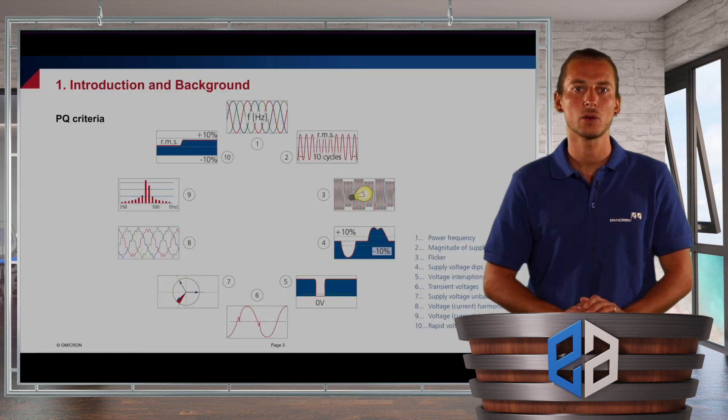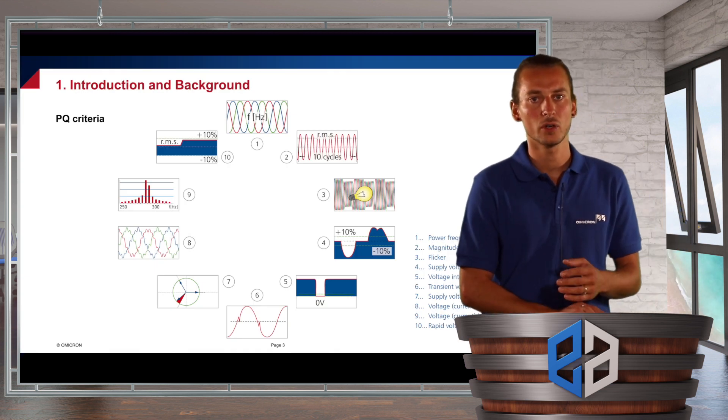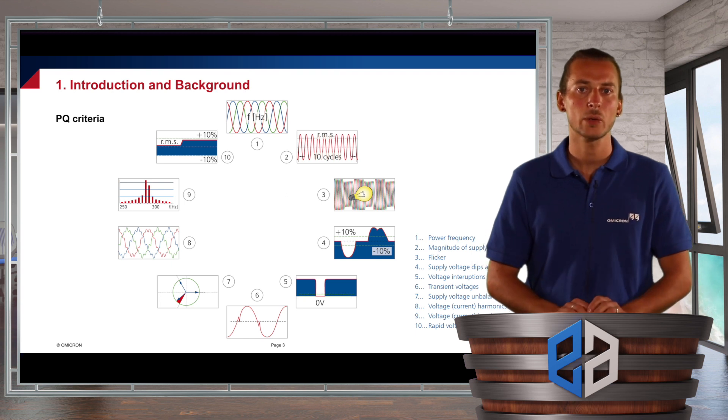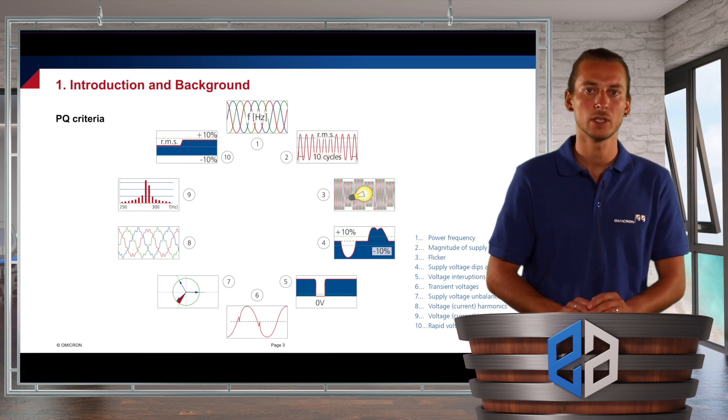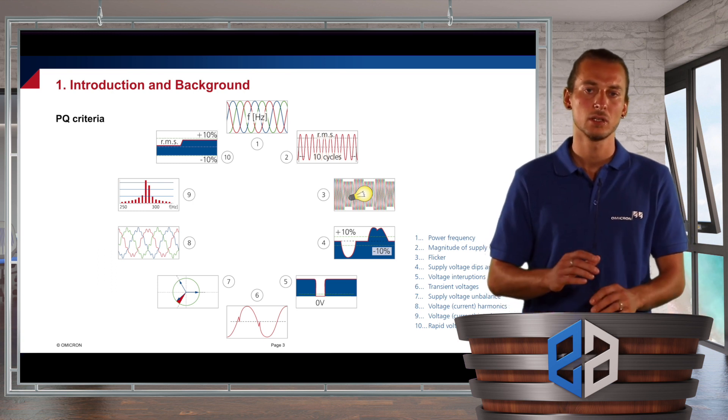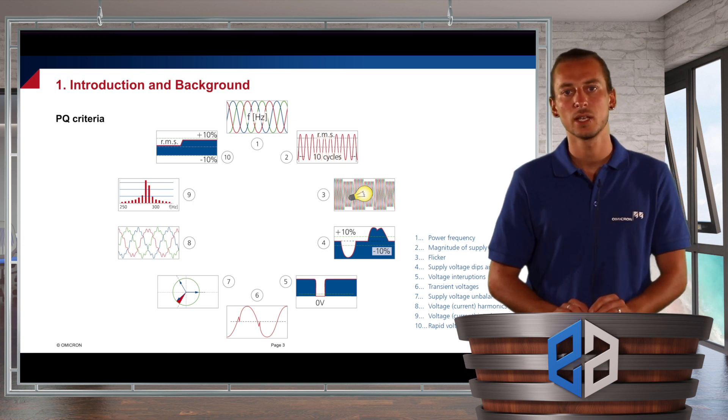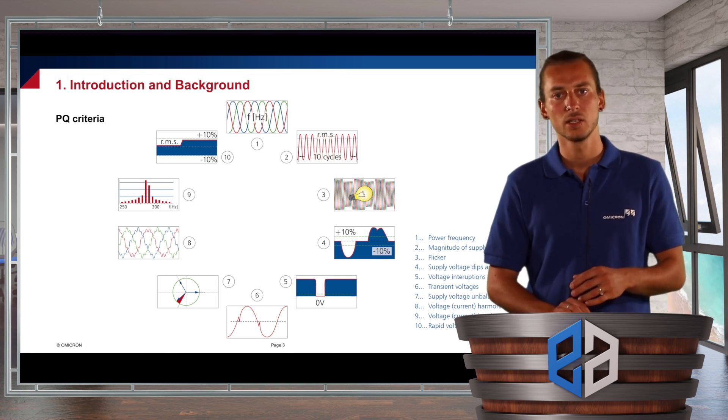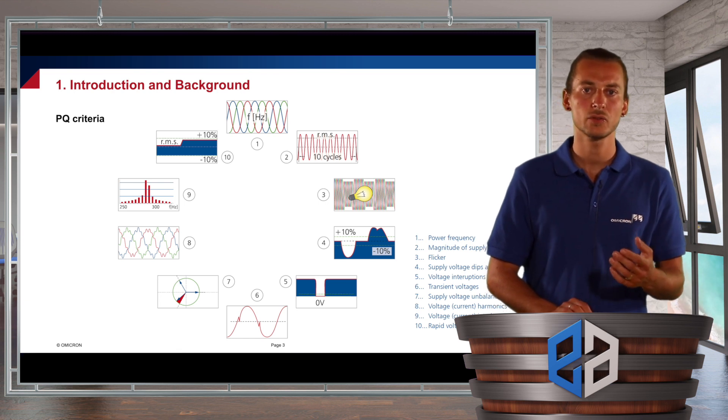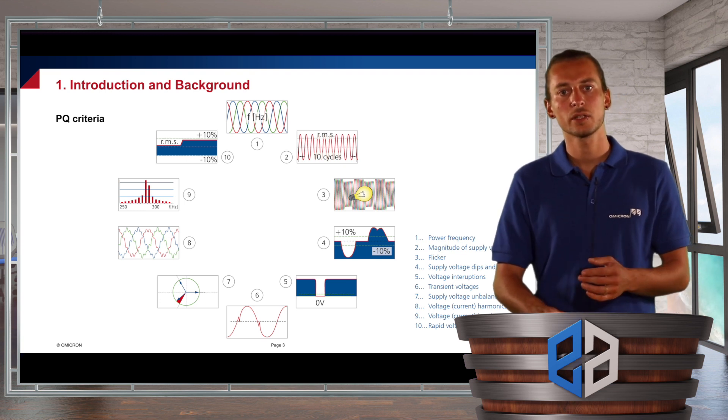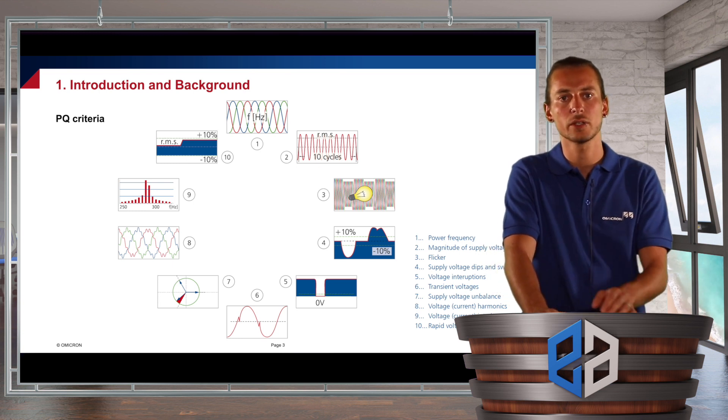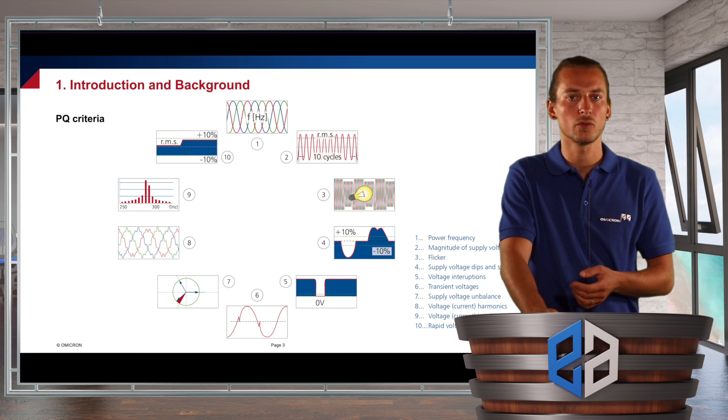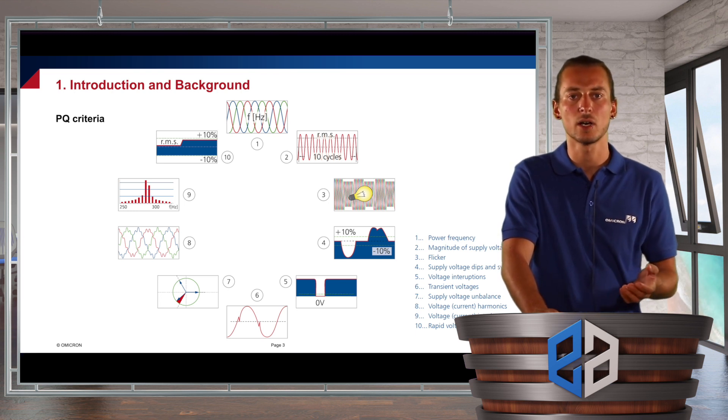Therefore, there are several power quality criteria defined. First of all there's the frequency. Then we have the magnitude of the voltage and current. We have flicker, which are short-term voltage fluctuations. Then we have long-term voltage fluctuations like dips or swells. And we even have interruptions. There are transient voltages and very fast rapid voltage changes. Then there's voltage or current unbalance. And of course, there are harmonics and interharmonics.